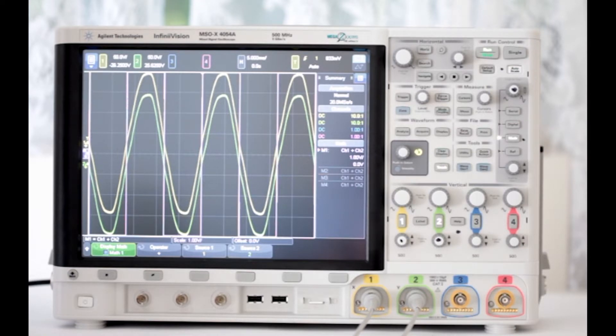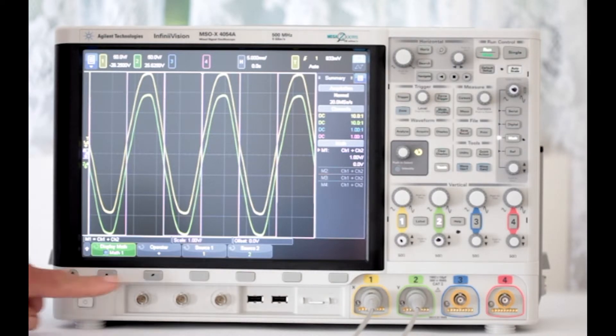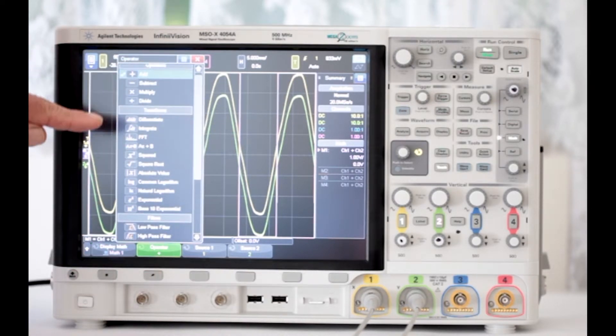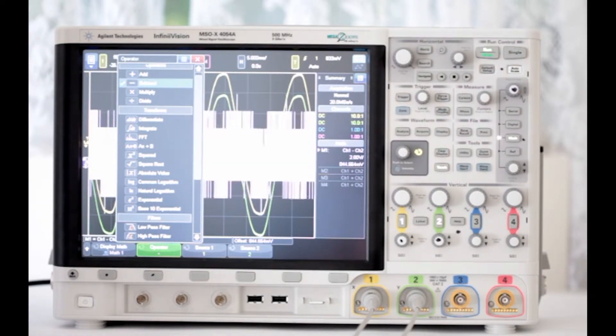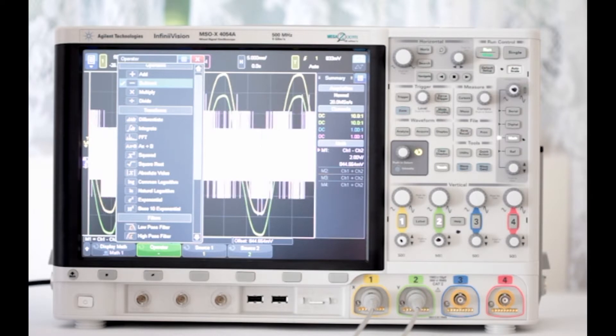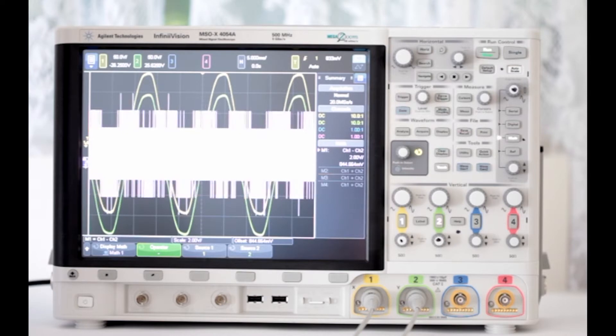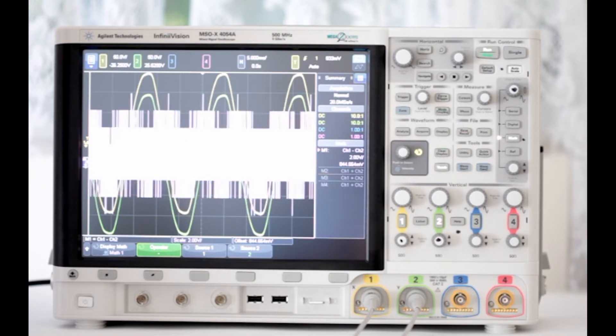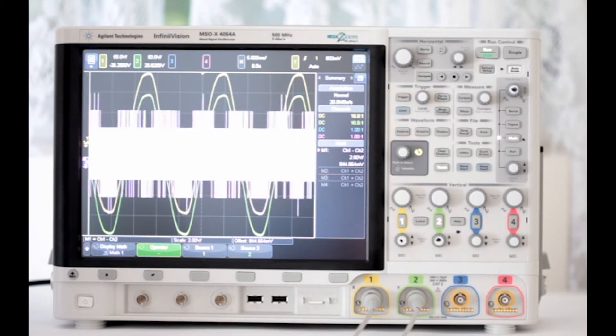We can display the add, subtract, multiply, and divide functions by using the selection knob, touch screen, or by pressing the operator soft key. You may think that the subtract display looks strange. We are seeing a zoomed in view of the noise floor. What's happening is that since the two analog inputs are equal at every point in time, the result of the subtract operation is always zero. Consequently, there is a very pronounced noise floor. The display, not the actual result of the operation, can be changed by adjusting the scale knob that is grouped with the math button.